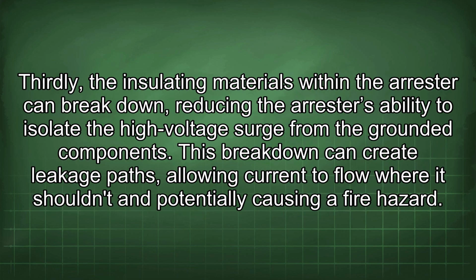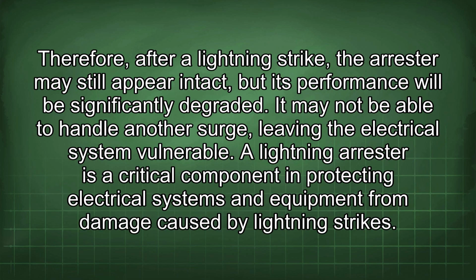Thirdly, the insulating materials within the arrestor can break down, reducing the arrestor's ability to isolate the high voltage surge from the grounded components. This breakdown can create leakage paths, allowing current to flow where it shouldn't and potentially causing a fire hazard. Therefore, after a lightning strike, the arrestor may still appear intact, but its performance will be significantly degraded. It may not be able to handle another surge, leaving the electrical system vulnerable.